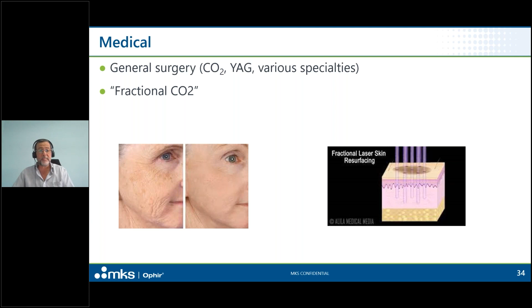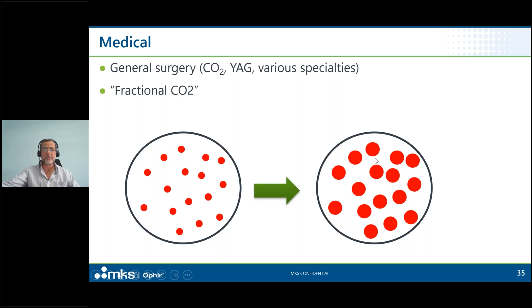Measuring this is usually based on the same type of thermal-based power sensors that we use to measure regular laser beams. When I first saw this some tens of years ago, my concern was that the localized power density inside these dots might be above the absorber's damage threshold, even if the overall average power density seems okay. The truth is it's not that difficult to calculate, and it turns out that the solution is very simple. As always, we want to defocus the beam. In a case like this, you don't want to defocus the beam too much because then it's going to expand beyond the aperture of your sensor. But it turns out that even a very slight defocus gives you a relative increase in the dot size that's more than enough to reduce the local power density inside the dot to the point where it's safely below the damage threshold, whereas the relative increase in the overall beam size is quite negligible. So that's something that we come across quite often.